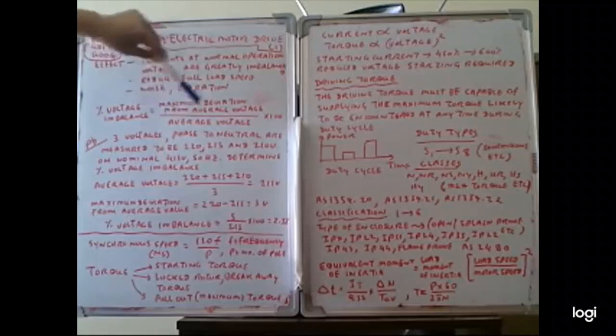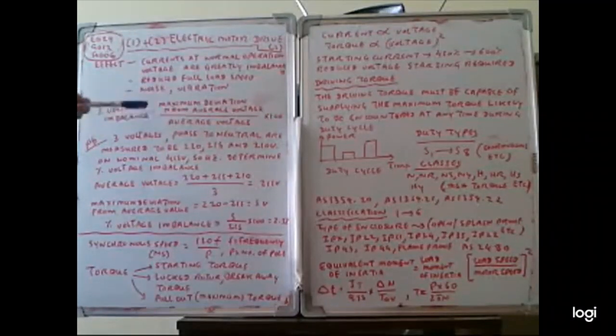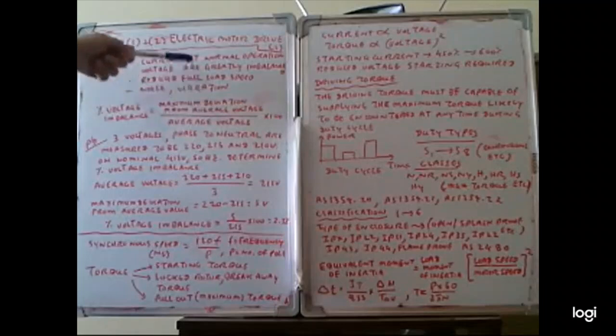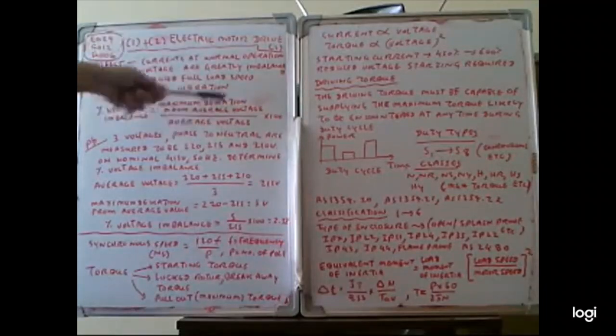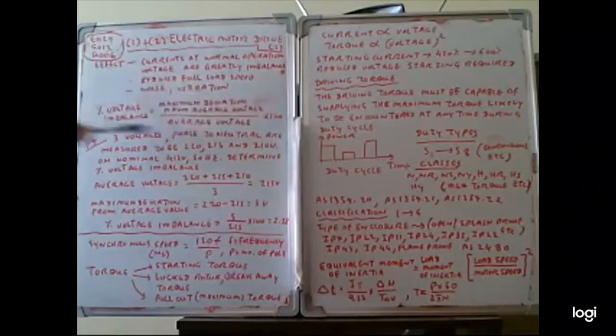The percent voltage imbalance can be calculated by a formula. The formula is the maximum deviation from the average voltage, divided by the average voltage, multiplied by 100. When the different voltages are given, we have to find the average voltage and then also find the maximum deviation. Maximum deviation divided by average voltage, multiplied by 100, gives you the percent voltage imbalance. Based on this formula, we calculated this problem.